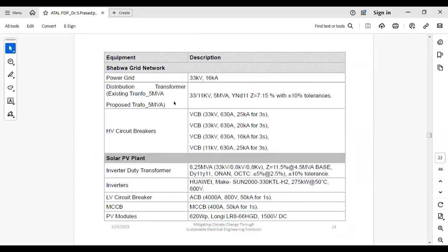The same system I have taken. You can see the same system, a 10 MVA PV plant. So the rating of this is a circuit breaker, VCB circuit breaker, which is basically used for a high voltage system. Vacuum circuit breaker, 33 kV, 630 ampere, 25 kilo ampere for 3 seconds. Okay, so those are the ratings of this vacuum circuit breaker.